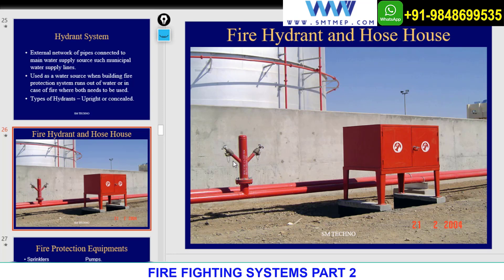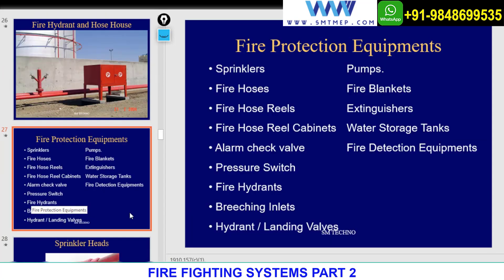Fire hydrants are located outside the building. Hydrants can be stand post type or different types, which is covered under NFPA 24. This is not a lengthy topic, but it's important. Generally, the hydrant is taken care of by the engineer responsible for the outside-building system. Depending on scope, the hydrant may not fall under the firefighting system scope — it can be handled by a separate engineer or contractor.